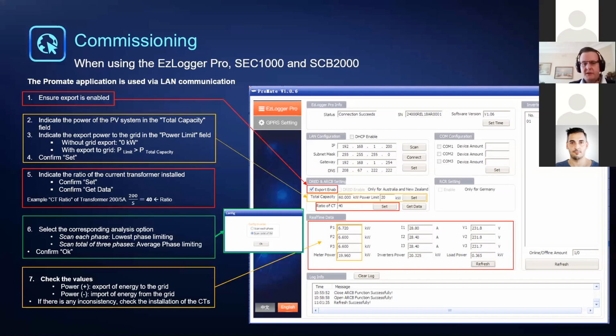It will open a pop-up window. And in that pop-up window, we can select the type of limiting that we like. So in most instances, we'll use the scan each phase, which will work on the lowest phase limiting. So that will limit to the lowest producing or lowest consuming phase. And then if a customer has net metering, which is measured on the HT side, you can use scan of total 3 phases, which is average phase limiting. With average phase limiting, you might find export on 1 or 2 of the phases, while importing on 1 of the phases.